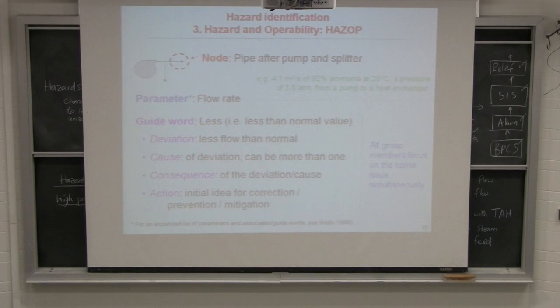So there's a whole table of guide words here on the next page. No or none, more or less, as well as reverse, other than. So not all of these make sense for flow, but one that does make sense for flow is less. More, no, reverse, those four make sense for flow. We're going to start with less flow. And once you've selected your node, parameter, and guide word, then we always look at this sequence shown here by the bullet points. So if your deviation is less flow than normal, what might cause that?